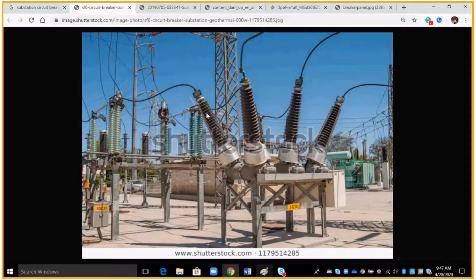Well, the simple way of doing that is if you have bushings that are the same size on both sides of it. This is 1, 2, 3 on the input, kind of blocked here, but in the picture is 1, 2, and 3 on the output, and they are the same size, then you know it's a breaker. There's no transformation going on inside this. This is just opening and closing as designed.